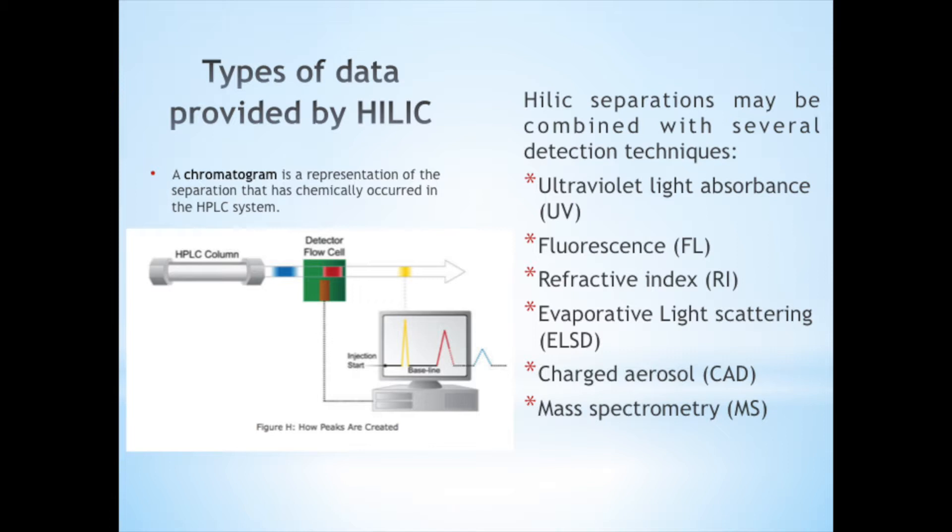For example, if a compound can absorb ultraviolet light, a UV absorbance detector is used. If the compound fluoresces, a fluorescence detector is used. If the compound does not have either of these characteristics, a more universal type of detector is used, such as an evaporative light scattering detector. For example, a UV or ELSD detector may be used in combination with a mass spectrometer to analyze the results of a chromatographic separation. This provides, from a single injection, more comprehensive information about the analyte.